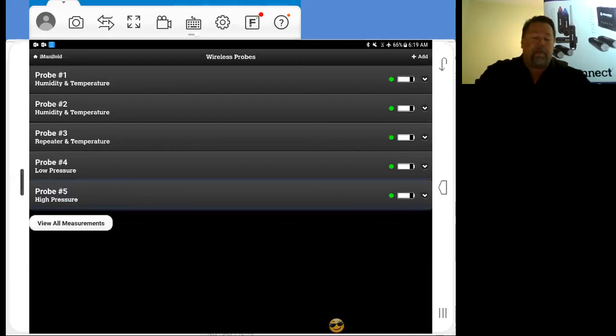On our low side probe, me using iConnect right now, I need a place to put my outdoor air temperature as well. So on this low side probe, I'm going to use T1 for my suction line temp. And for T2, I'm going to use my 903M, which is the 12-foot long sensor, so I can get this thing into good neutral condensing air. And we'll plug that into T2 on the low side probe.